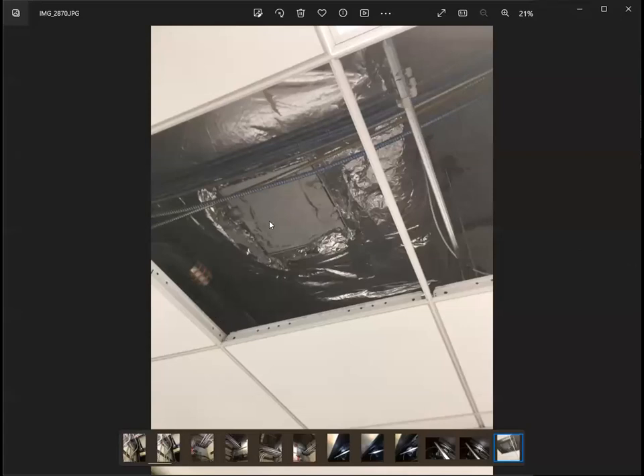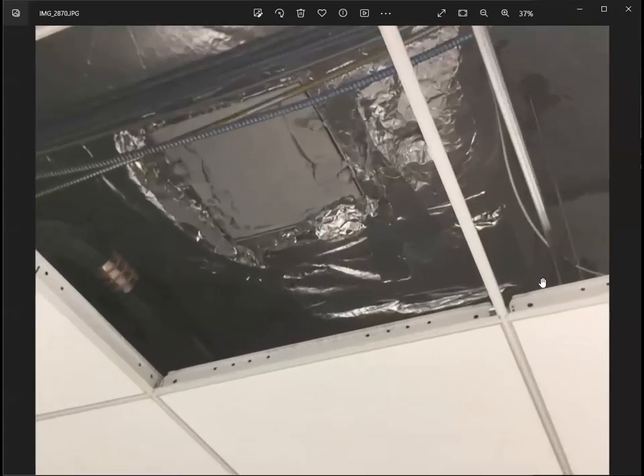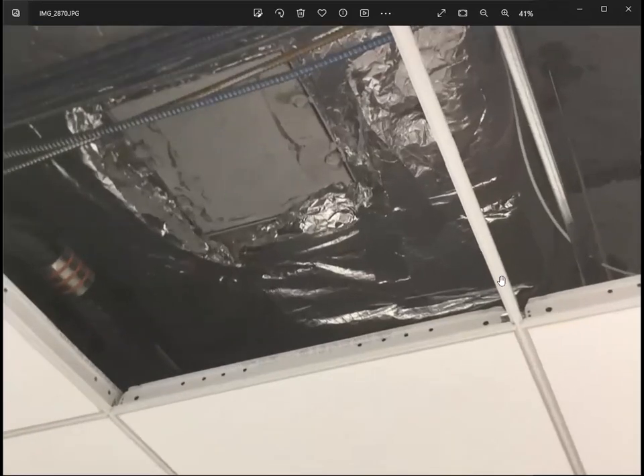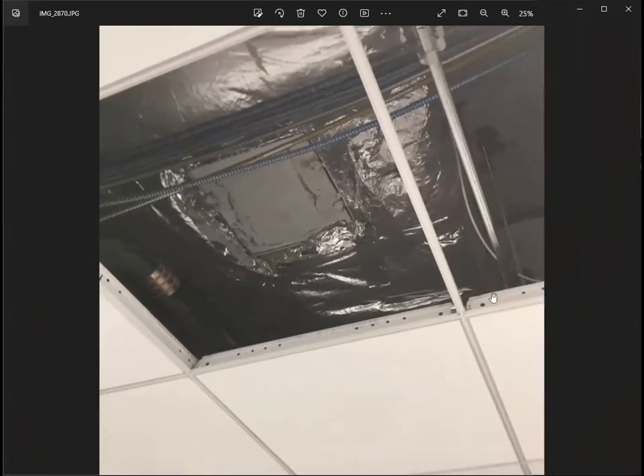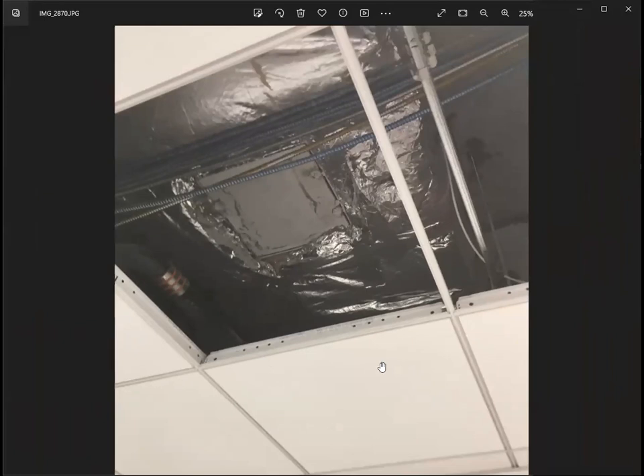And this, I took a photo of this because I believe this is an access door. Access door should be provided in every fire damper. So you can see here, this duct penetrates a wall. So probably that wall has a fire rating, and every new duct should have a fire damper inside of it. So this is an access door to access the fire damper.